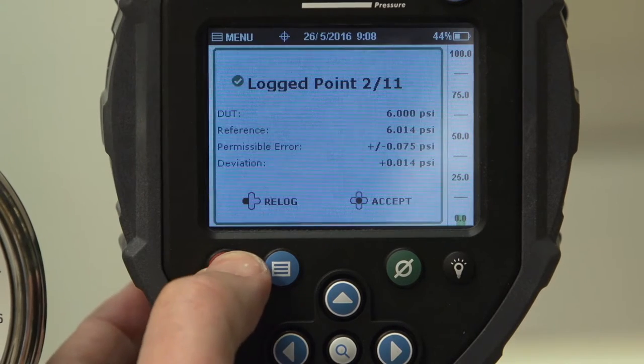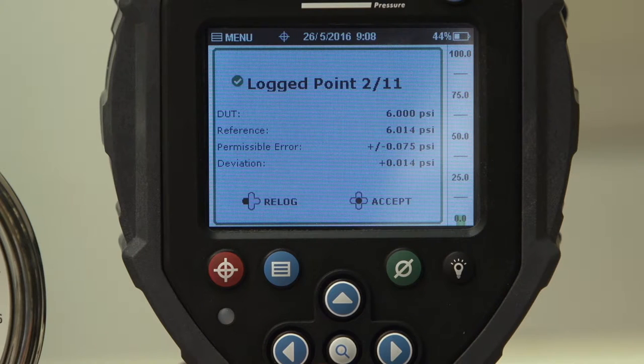Now we press log and you see a summary of the test point. Notice that both the reference and DUT readings are logged along with the computed deviation. We can also see that this point was within the permissible error for this device.